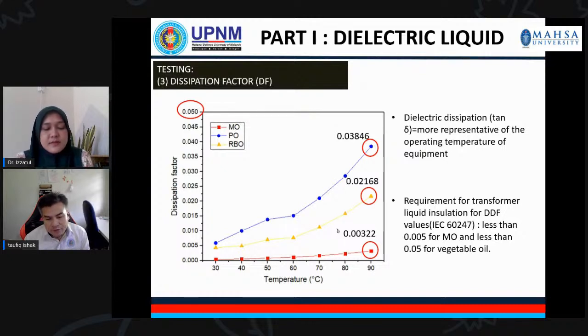This dissipation factor actually measures how efficient the insulation liquid is, and it can be a great indication of contamination or deterioration of your liquid insulation. So when you have a lower dissipation factor, it means that you have a better insulation material. For this case, as you can see from the study, at 90 degrees C, the rice bran oil has a 0.02168 dissipation factor, which is 7 times larger than mineral oil. Whereas for palm oil, the dissipation factor is 12 times higher than mineral oil.